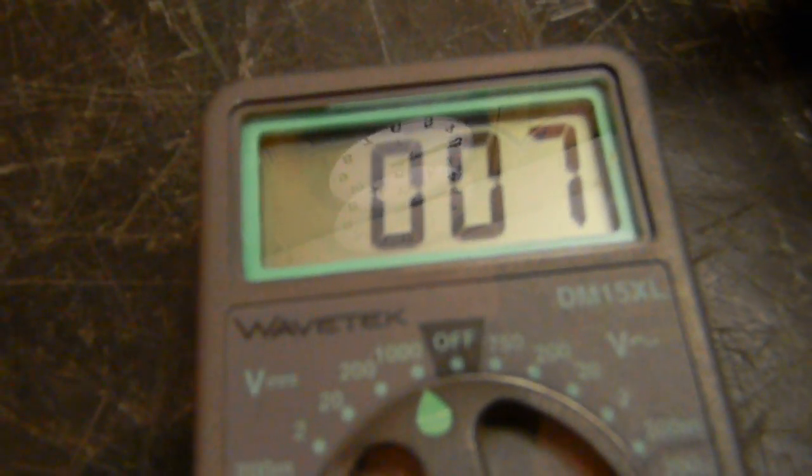But unless you give the thing time to warm up before you turn it back off, if you turn it on even for a fraction of a second, a solid-state power supply is going to charge the big power supply capacitors up to full voltage—even worse, they're going to charge it up to the peak of the sine wave. So you turn it on, turn it off, stick your hand in, and get blasted.